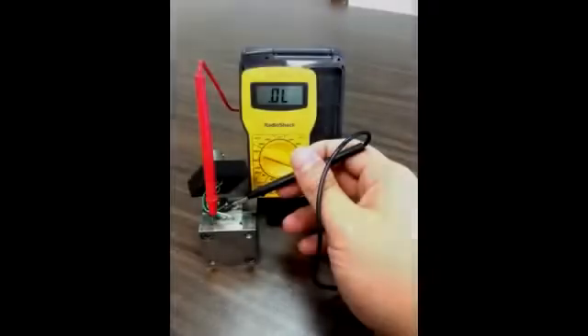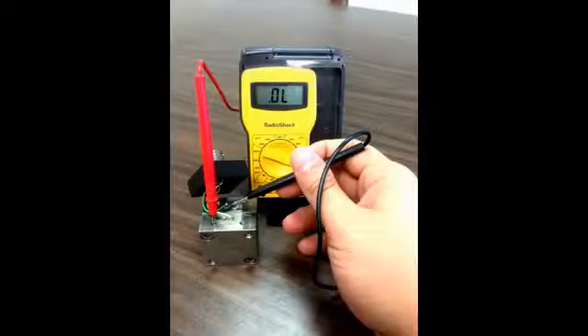The next step is to measure the isolation resistance between the black wire and the sensor body. Set the multimeter to read resistance on its highest setting, we are expecting a very high resistance here. A normal reading is several hundred megohms or open circuit.